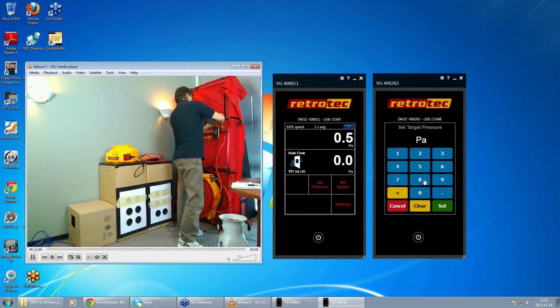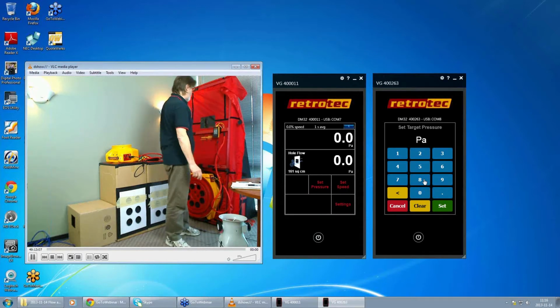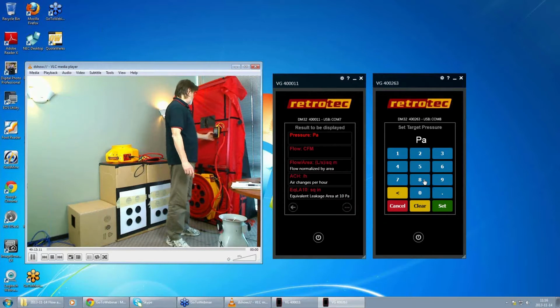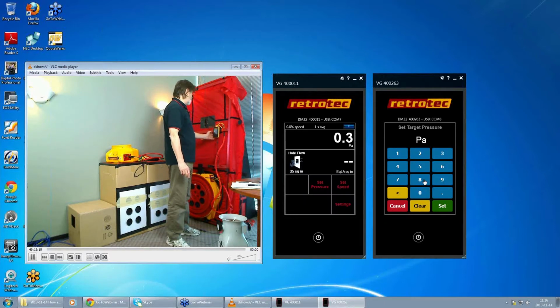So we're just going to hook the tubes up here. And to do this, a really easy way is to use EQLA. I like to test at 25 pascals, so we're going to change the settings on here to equivalent leakage area, EQLA, and we're going to do this at 25 pascals.